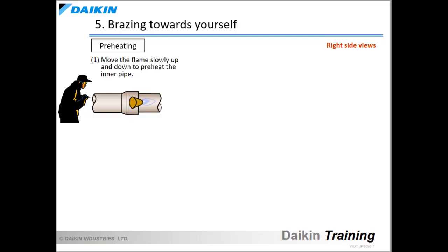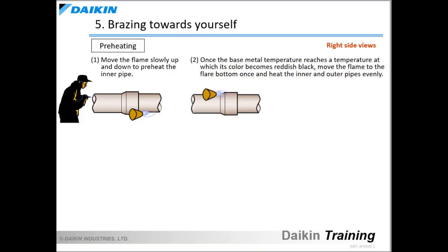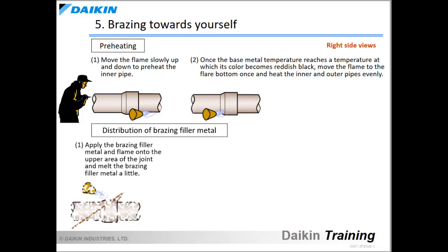Move the flame slowly up and down while keeping it above the inner pipe. Place the flame so that the distance between the carbonizing flame tip and copper pipe is 0.08 to 0.12 inches. Place the flame 0.2 to 0.4 inches from the flare end on the copper pipe at a 90-degree angle. Once the color of the base metal becomes reddish-black, slowly move the flame from the top downward along the flare bottom once to heat the brazing area evenly. When the inner and outer pipes reach the appropriate temperature and are heated evenly, start distributing the brazing filler metal.